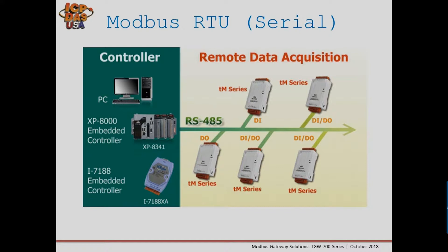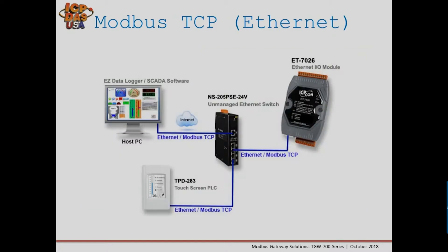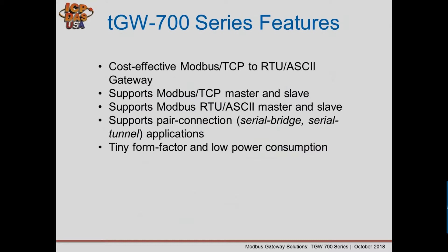A typical Modbus RTU application has a controller, PLC, or Modbus master device connected via RS-485 to several slave devices daisy-chained along a single bus. Modbus TCP on the other hand has a master device connected through Ethernet to an Ethernet switch, with Modbus TCP slave devices also connected through the Ethernet network.